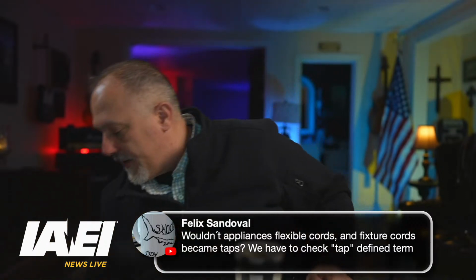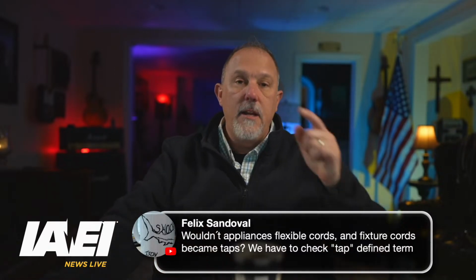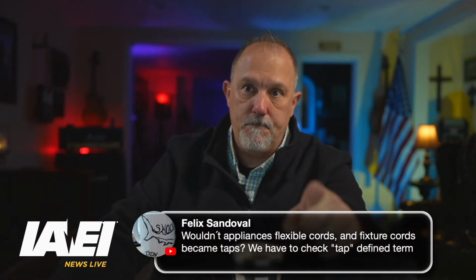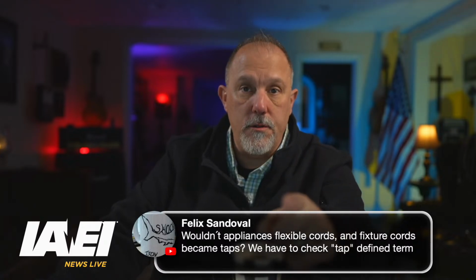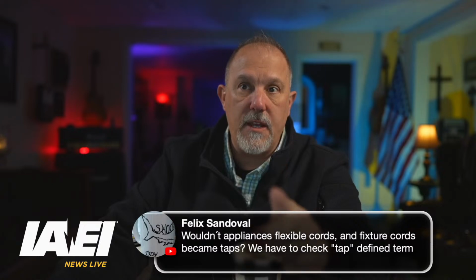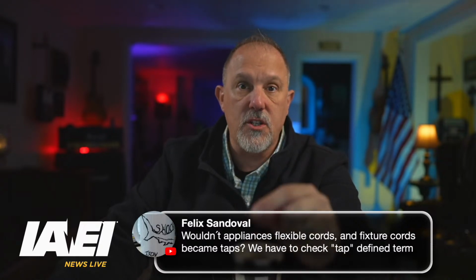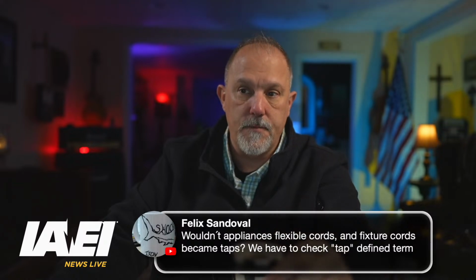Here's my thought on that, Felix. I'm trying to think of how I would address that. Here's my thought. I don't think you're wrong. I think it would meet the definition of a tap conductor because it's not protected at its source.